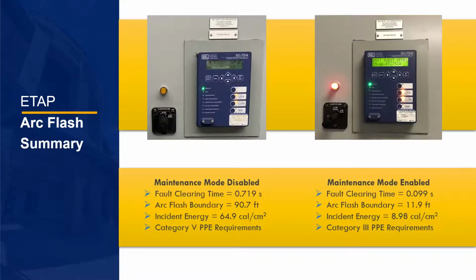To provide a summary of the arc flash study, prior to enabling maintenance mode switches, we see dangerously high energies and a very large arc flash boundary. When the arc flash maintenance mode is turned on, the relay trip time decreases to less than 1/10 of a second, reducing energies to just over 8 calories per centimeter squared and the boundary to 12 feet. The fault clearing time considers the number of cycles it will take the relay to detect the fault and how long it will take for the breaker to open and clear the fault. We can see a significant improvement over the system without maintenance mode enabled.